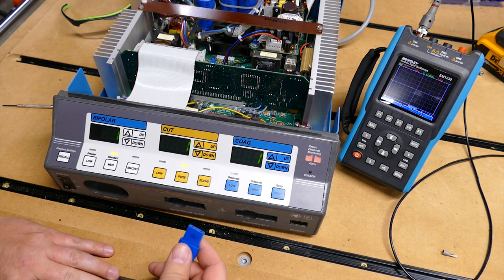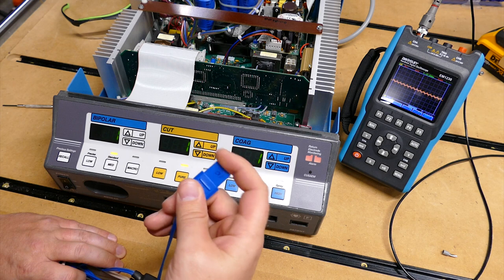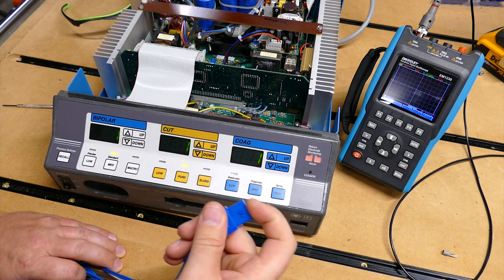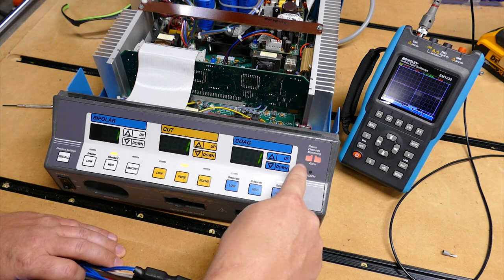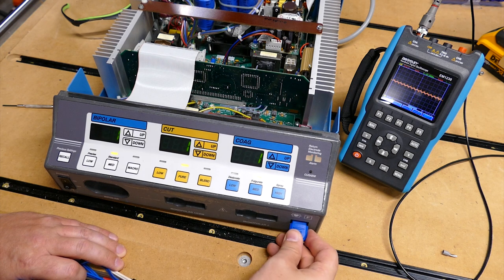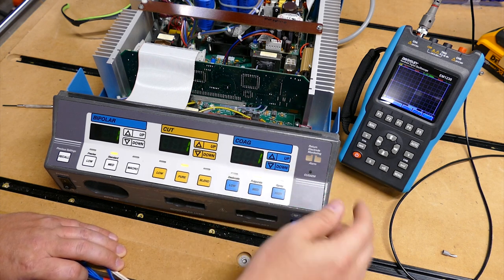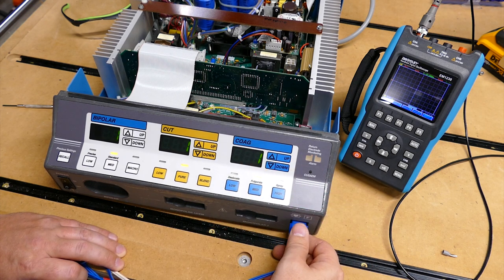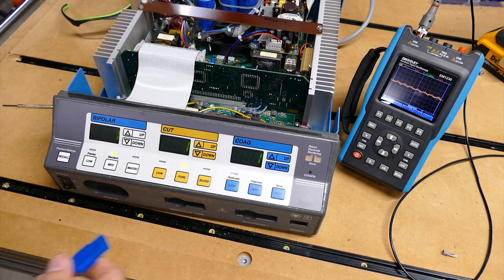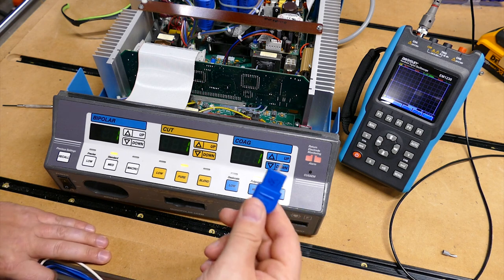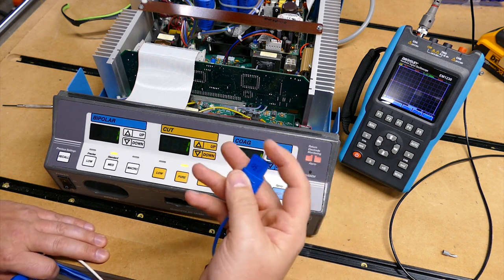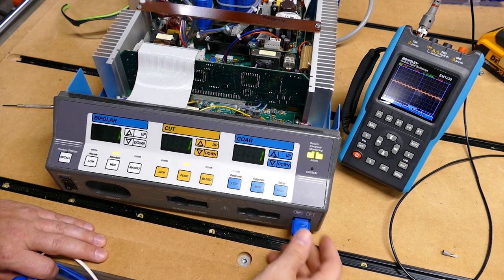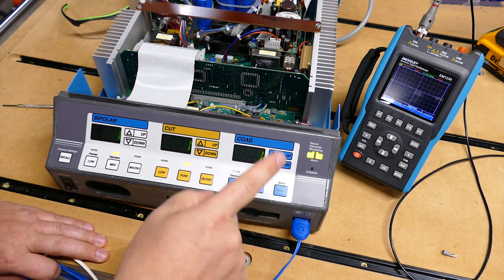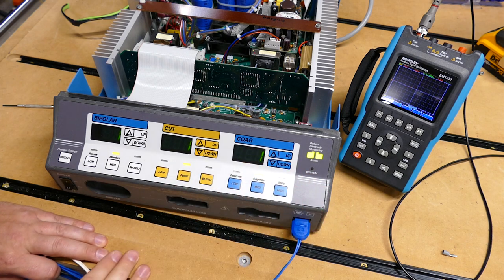Okay, the first test I'm going to do is with the 10 ohm key. It does not have the little probe that tells it it's a dual pad. So what you should see is this should just go off. No alarms being shown. It just goes off. Then I'm going to jump up to 130 ohms with the little dongle on there. You see, before it was failing this test, now it's clearly showing green. We're good to go.